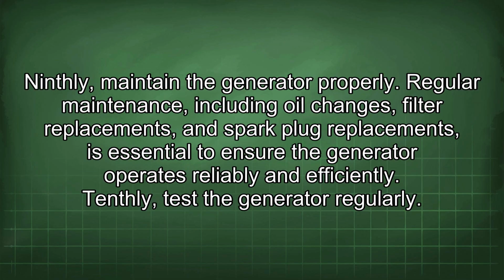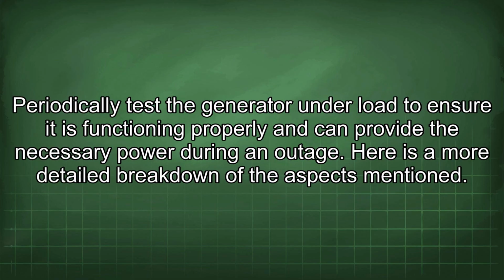Ninthly, maintain the generator properly. Regular maintenance, including oil changes, filter replacements, and spark plug replacements, is essential to ensure the generator operates reliably and efficiently. Tenthly, test the generator regularly. Periodically test the generator under load to ensure it is functioning properly and can provide the necessary power during an outage. Here is a more detailed breakdown of the aspects mentioned.